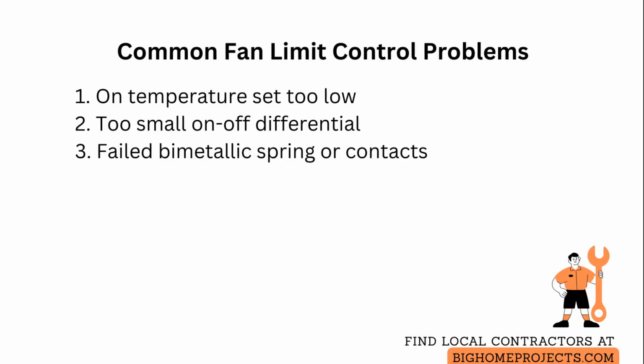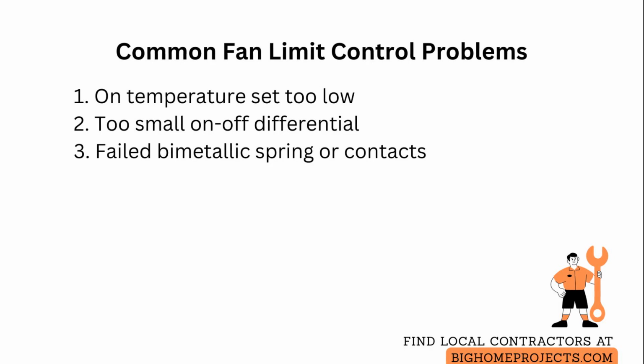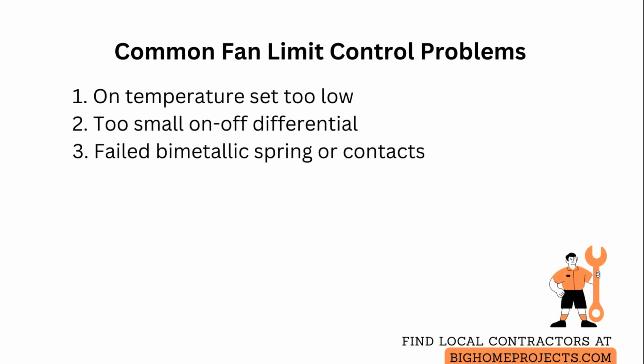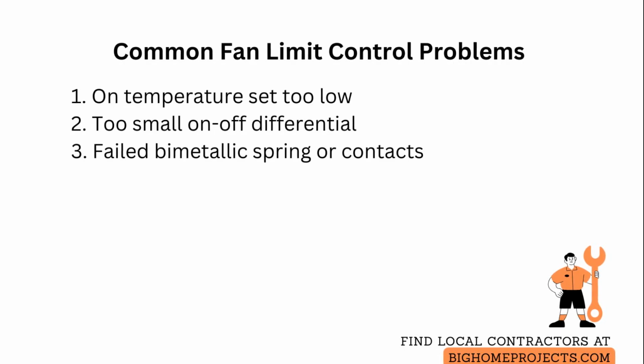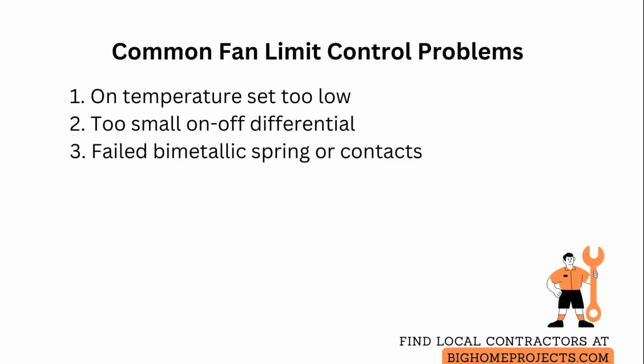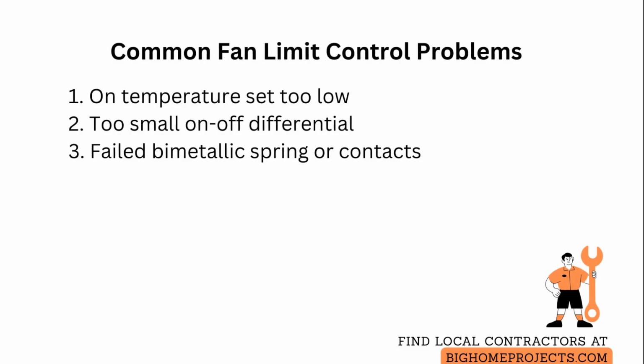Another frequent issue is an on-to-off differential that is too small, causing short cycling of the blower. Increase the off threshold to between 85 and 90 degrees, so the blower runs long enough to move heat effectively. Finally, a failed bimetallic spring or dirty control contacts can make the blower ignore the settings. If cleaning the contacts does not restore proper function, replace the entire limit control.